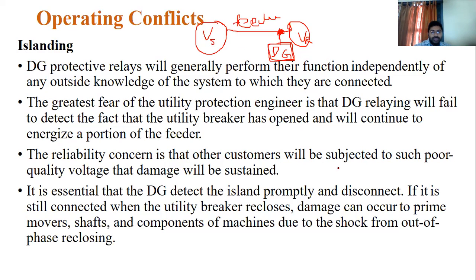So yes, you need to protect the feeder separately and, at the same time, the DG separately. That means you need to maintain separate protective schemes for both the feeders and the DGs. Here, this DG protection, especially talking about this DG protection. Now see this point: DG protective relays will generally perform their function independently, without knowledge of the system to which they are connected.